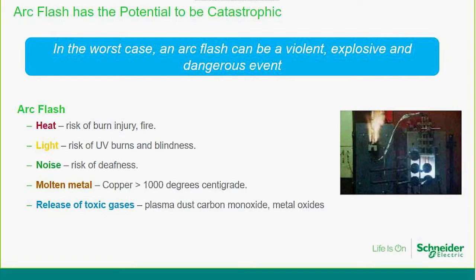So I know from my career, I've been involved in an incident once when somebody was working above a 6,300 amp air circuit breaker inside a panel. They weren't really doing anything wrong. It's just that the breaker cleared a fault whilst they were leaning over the top of it. And I'm afraid all of that energy involved in clearing that fault was dissipated into their chest. So there are questions as to why they were working in that panel in the first place when the equipment was live. But we have to try and understand the risks associated with being anywhere near it, because it can happen at any time, as we well know with electrical faults.